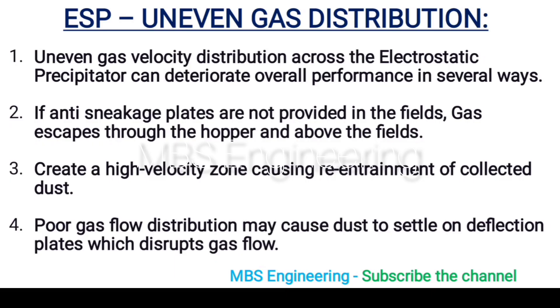Now we understand what are the problems faced if there is uneven gas distribution in the electrostatic precipitator. Point 1: Uneven gas velocity distribution across the electrostatic precipitator can deteriorate overall performance in several ways. Point 2: If anti-sneakage plates are not provided in the fields, gas escapes through the hopper and above the fields. Point 3: This creates a high velocity zone causing re-entrainment of collected dust. Point 4: Poor gas flow distribution may cause dust to settle on deflection plates, which disrupts gas flow.